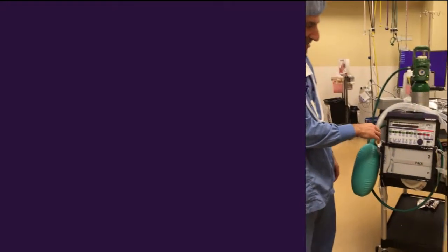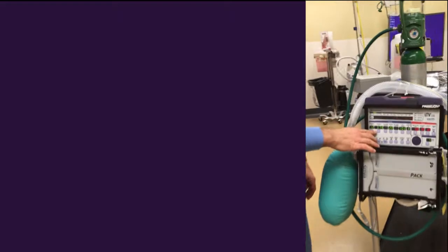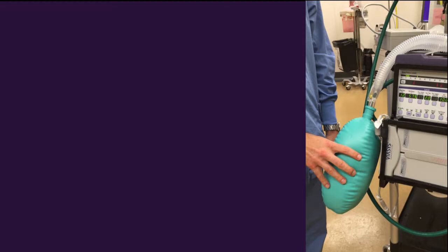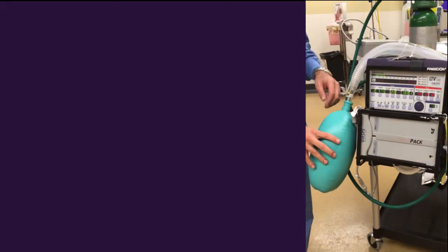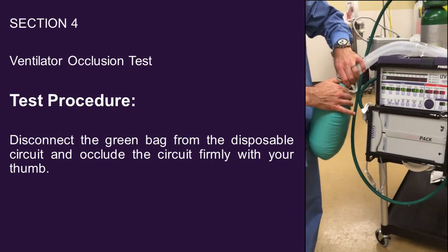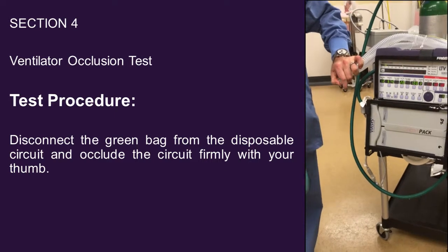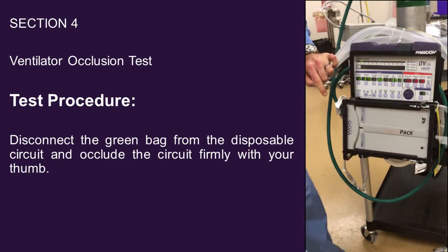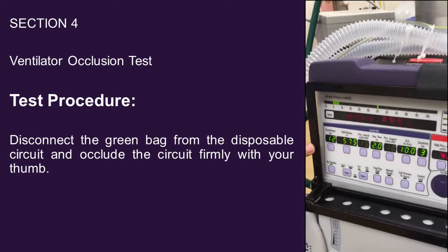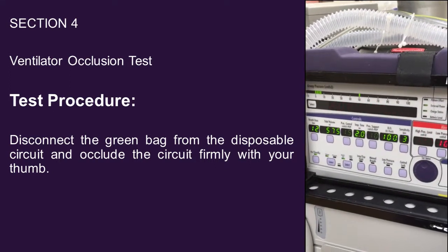In this particular case, you can see that the tidal volume here is set at 575 mLs. You can see that the high pressure limit is defaulted to 40 centimeters of water. We've got a green bag which represents the lung, and all is well. I'm going to disconnect and simply occlude the circuit with my thumb, and you'll note that immediately the high pressure alarm goes off and the volume is not delivered.